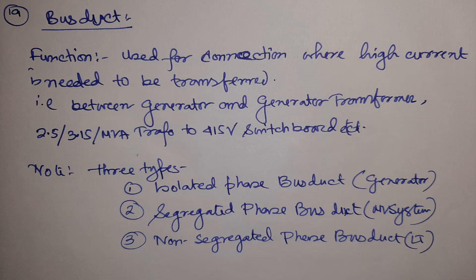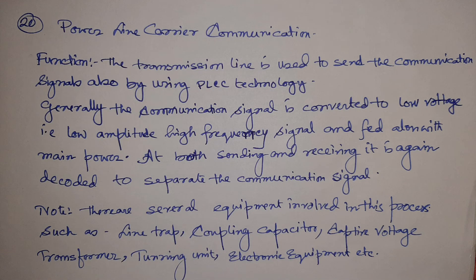Bus ducts are of three types: isolated phase bus duct, segregated phase bus duct, and non-segregated phase bus duct. Isolated phase bus duct is used for generators; segregated phase bus duct is used for MV systems such as 6.6 kV and 11 kV; and for LT systems at 415 volts, non-segregated phase bus ducts are used. I have a video on bus duct — you can check that for more details.